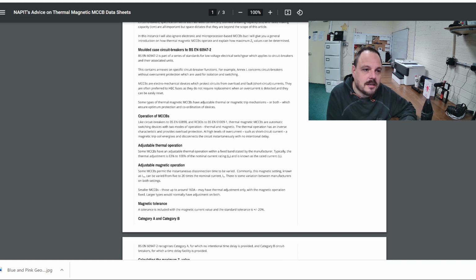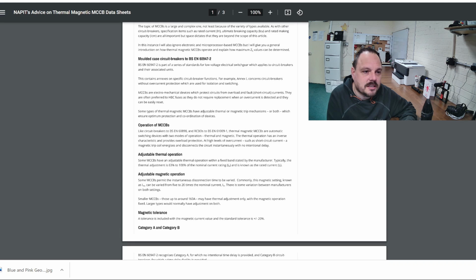can be determined. So if we look at the moulded case circuit breakers, it's saying here that the actual BS number is a part of the standards for the low voltage electrical switchgear, which applies to circuit breakers and their associated units. This contains annexes of specific circuit breaker functions. For example, Annex L concerns circuit breakers without overcurrent protection. MCCBs are electromechanical devices which protect circuits from overload and fault short circuit currents. They are often preferred to your HBC fuses as they do not require replacements when an overcurrent is detected, and they can be easily reset.